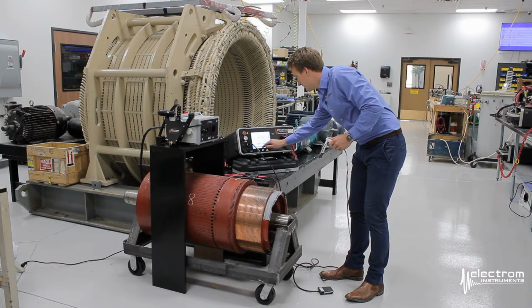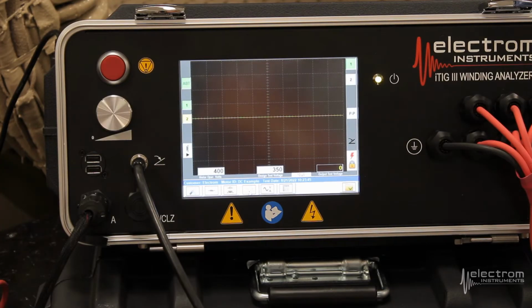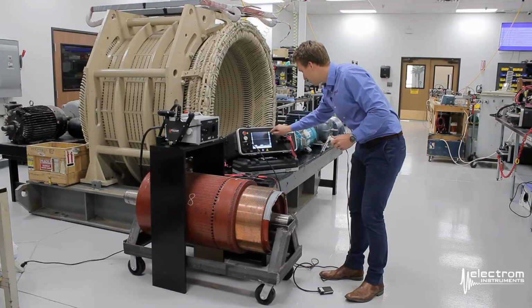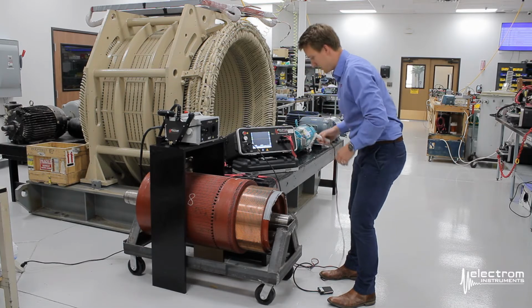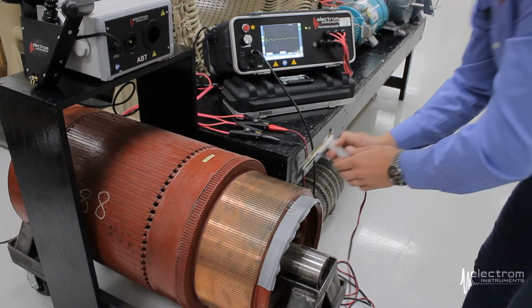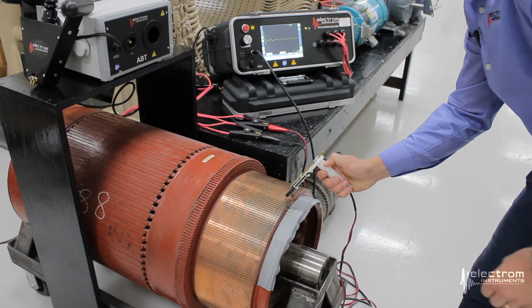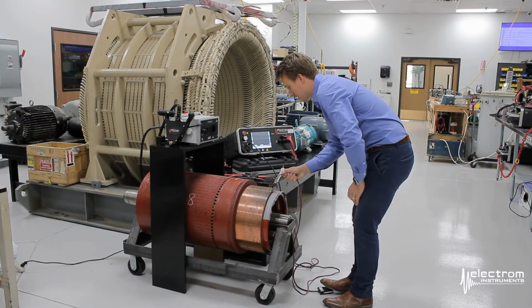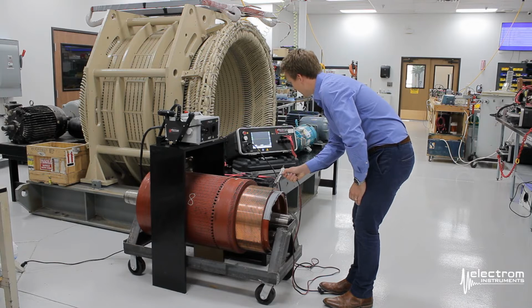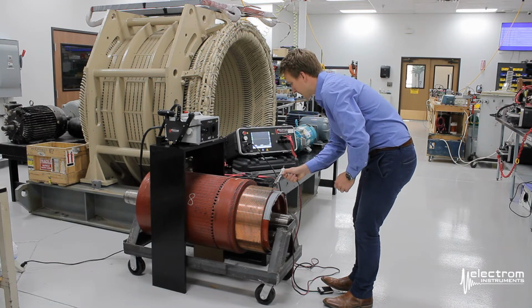We go to the surge screen. We arm the instrument. You can see we're on record number 1 in the top right corner here. Find a good position, span across your 5 bars, step on the foot pedal, and let the instrument do its job. Okay, we have our first test here.